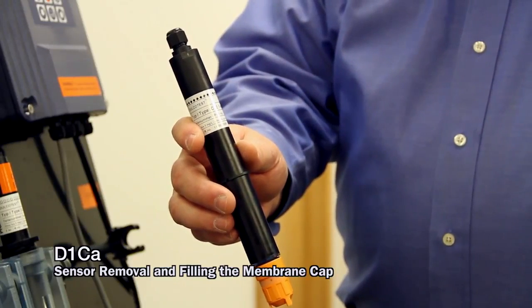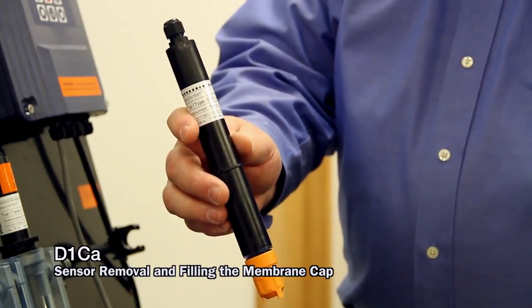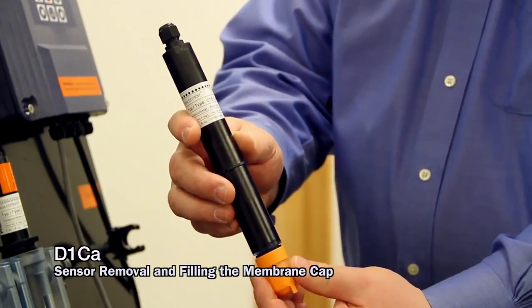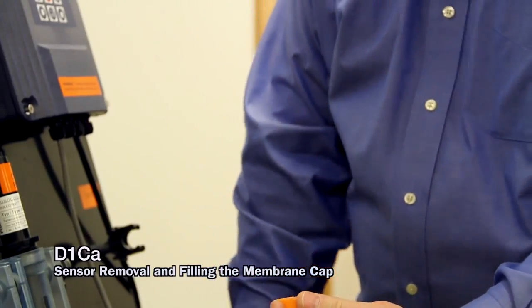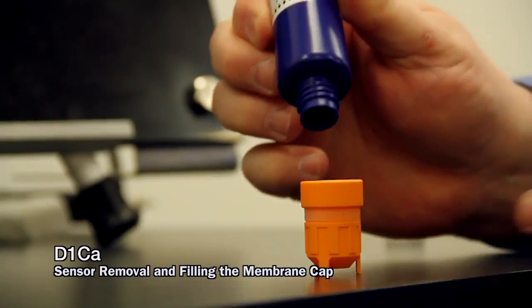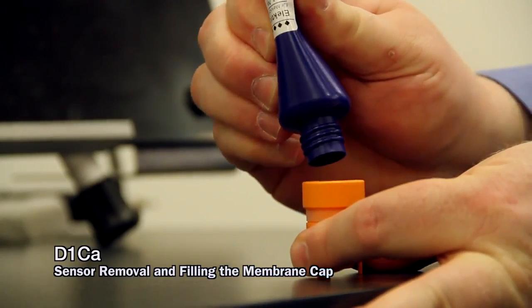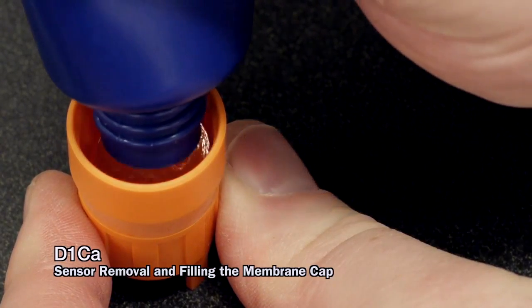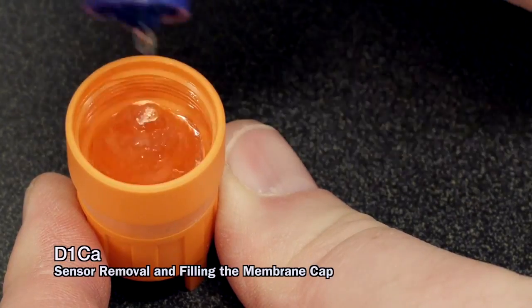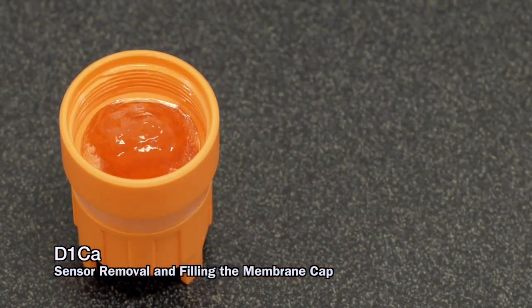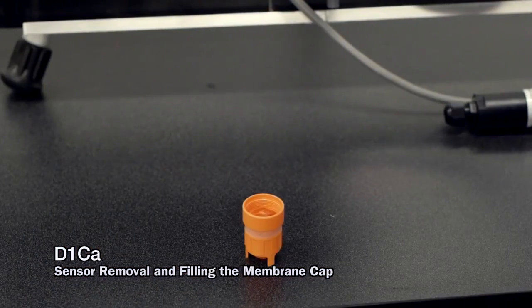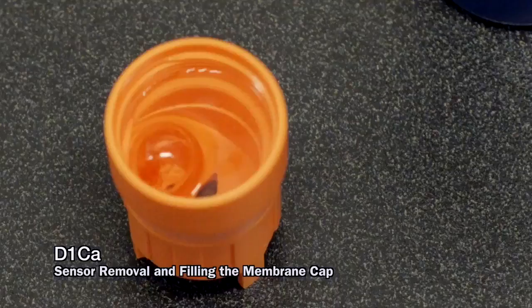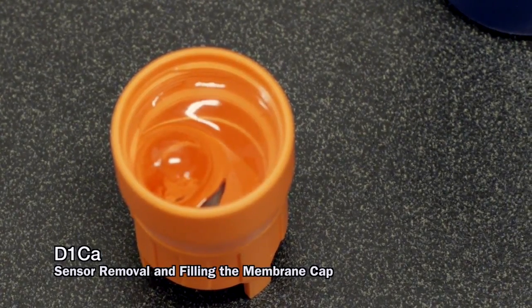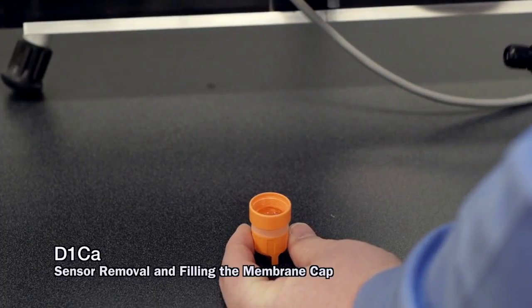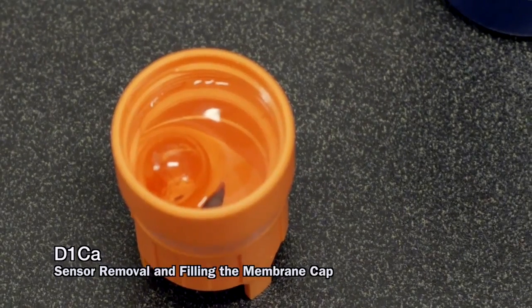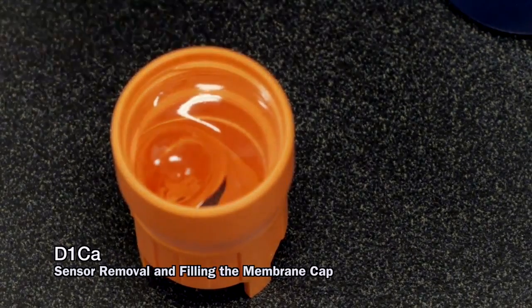Some of our sensors have electrolyte that is a bit more viscous, so to change or to add the electrolyte in that, again, we're going to remove that cap. We're going to fill that cap with electrolyte. Here you can see how much thicker the electrolyte is. We want to fill it again so there's no air bubbles. If there is an air bubble, that air bubble will migrate towards the top in time. We'll let that come to the top. Never put a screwdriver or any other instrument into the electrolyte. If you want to try to help remove the air bubble, use the sensor tip itself.